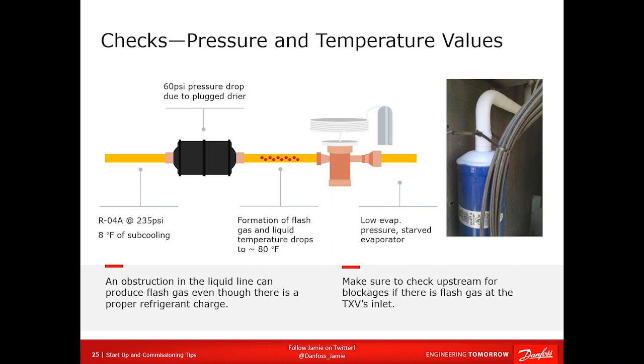So if you've got flash gas at your metering device and liquid leaving your condenser, you need to figure out where it went. Just like you would if you had 24 volts at your control transformer or 26 volts, 0 volts at your compressor relay coil, you've got to figure out where it went. What is open in this case that's stopping my voltage? Well, in this case, you're looking for what's closed or plugged that's getting rid of your subcooling.